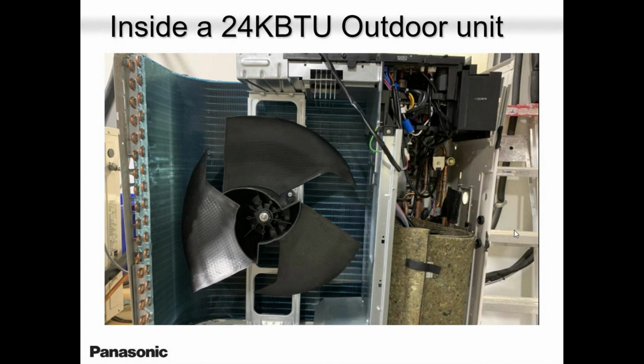That picture I took is based on our last session. A guy was asking, I wanted some more pictures to see what is inside the unit. So that section there, guys, if you can see my cursor, from here all the way here is one piece, the outdoor unit PCB. Control, inverter, everything is built in one piece. You have a problem with the board, change the entire board, get a new board, replace it, up and running. Down here, this is a 24,000 BTU unit.